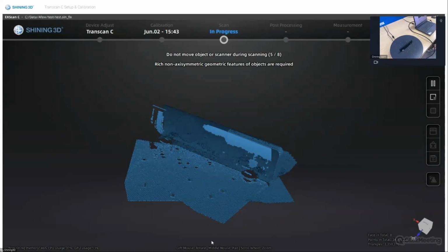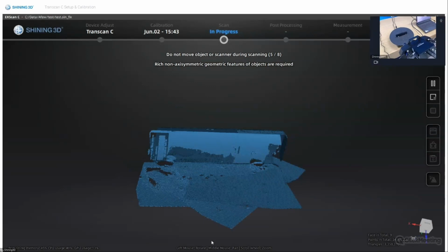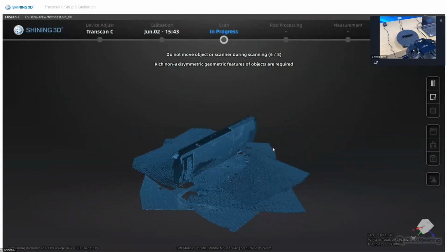Yeah, the software is a little bit slower than the scanning process. This is usually because for a 150 millimeter range, the data size for each scan is really large. So the points that you collect for each shot are really a lot. And to process the data, like I said, the computer I use has only 16 gigabytes of memory, and it's not using the best graphic card you can get, so it's still a little bit slow.